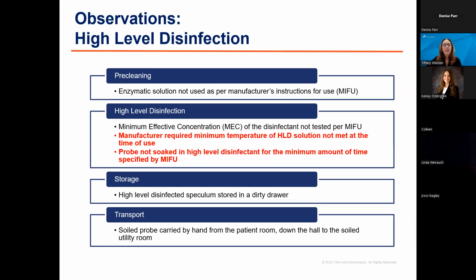But these two items in the red here are really what I want to show you, right? Because this is, again, where immediate threat to health and safety is evaluated and sometimes gets called. So: the manufacturer-required minimum temperature of the high-level disinfection solution not met at the time of use. Manufacturers of several of the high-level disinfectant solutions say the solution has to be at least a specific temperature at the time of use. We have queried them multiple times, every couple months, to see if anything has changed. They have not endorsed that if it's used even half a degree colder, it has high-level disinfected that item. So if the manufacturer says the minimum temperature is 68 degrees, the temperature of the solution has to be at minimum 68 degrees at the time of use.